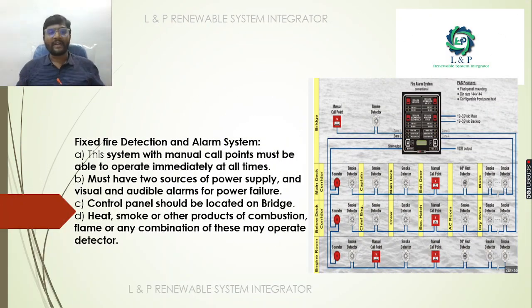So during the fire alarm detection in the alarm system, the system should have manual call points. It should operate immediately at all times. And most importantly, if you are providing the power supply to these fire alarm control panels, it should have a redundant power supply. It should have two sources of power supply. If a failure occurs in one system, the other system should operate. And also, most importantly, the control panel should be located on the bridge for easy access.